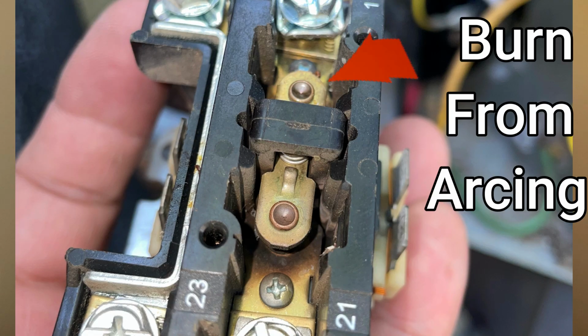Now, I'm not saying that this component has to be changed out once a year, and actually some contactors will last the full life of the system. However, in the same breath, we've had some units that we've needed to replace a contactor in 2 or 3 times. However, the problem with a contactor is it just ends up being out of sight, out of mind. So I would look out for pitting, which is signs of arcing, bugs living inside of it, and loud buzzing noises. So if you see or hear any of those things, I would recommend replacing it right away.